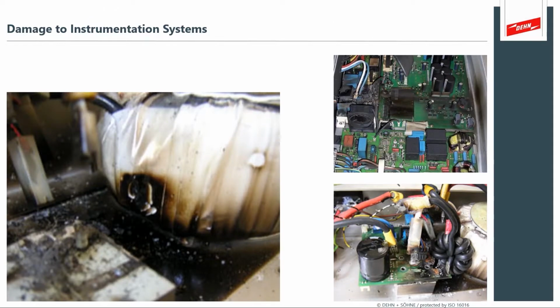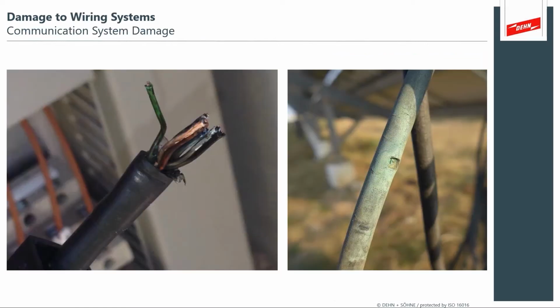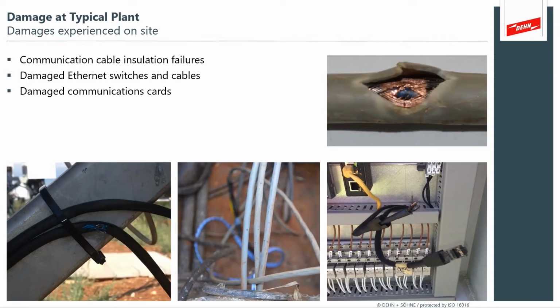You see a lot of damage to instrumentation systems, everything from blown up components to damage on circuit boards. You see damage to communication wiring. You'll see damage to power system wiring, and this can be particularly hard to troubleshoot and expensive to replace because it'll cause punctures in the wiring system that might require an extensive recabling of the wiring and power control systems. You'll see lots of damage to the communication wiring systems. It's really important to pay attention to not just the power and the high voltage cabling systems, but also to the power over Ethernet and low voltage communication systems.